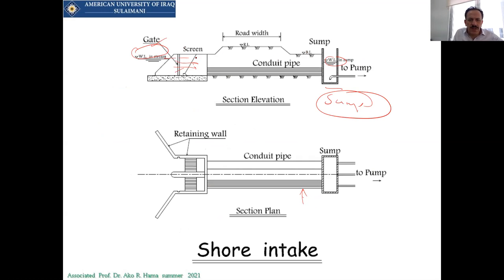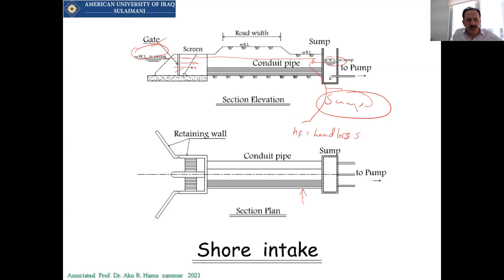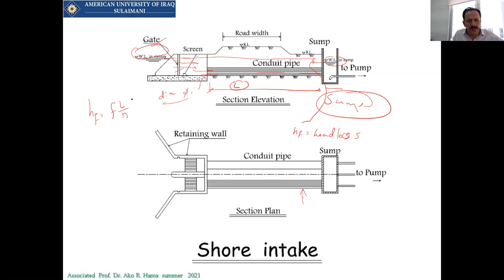The difference between the stream level and the sump level is due to head losses. The head loss occurs as water travels through the pipes over distance L. There is a friction head loss equal to f·(L/D)·(V²/2g), where V is the velocity of the water through the pipe, L is the pipe length, D is the pipe diameter, and f is the Darcy-Weisbach friction coefficient, typically between 0.01 and 0.02.